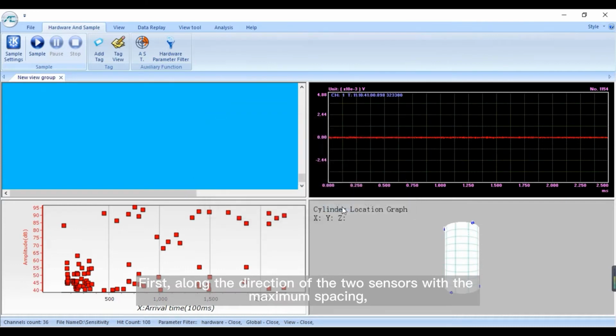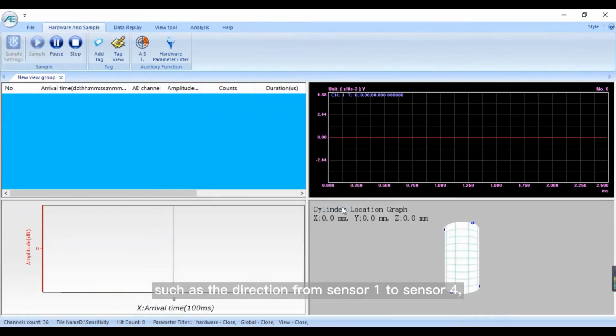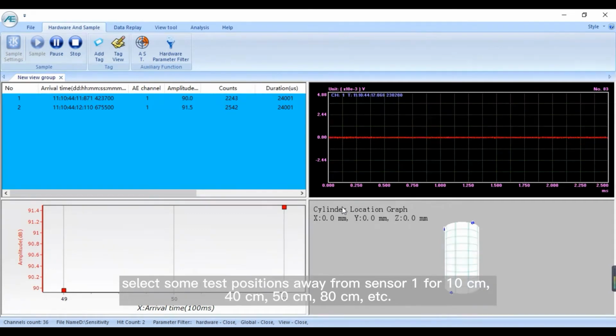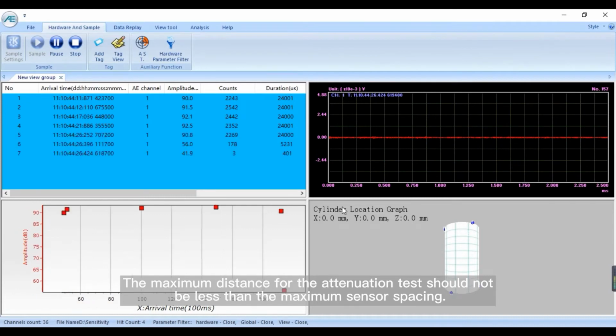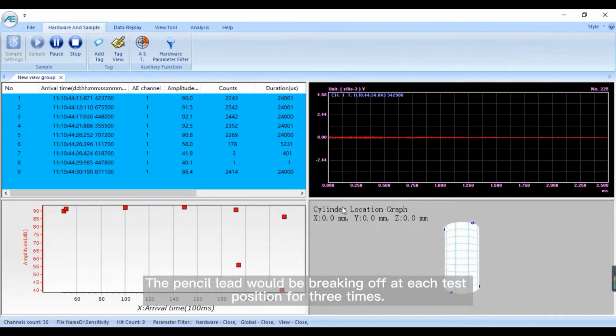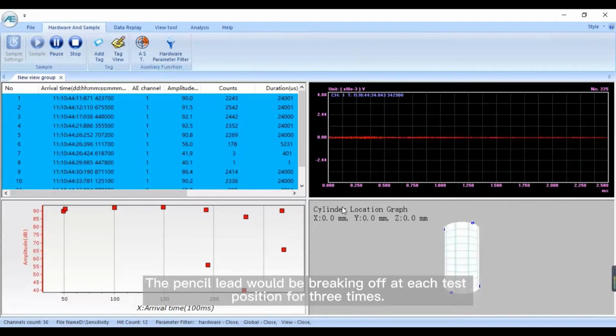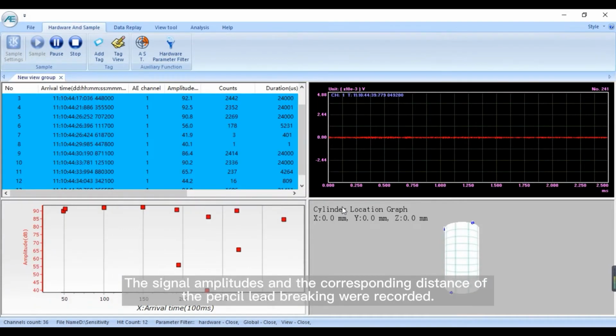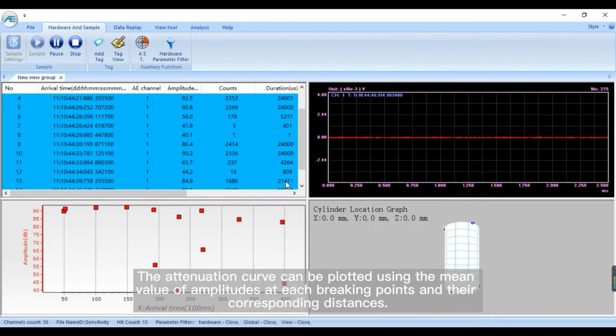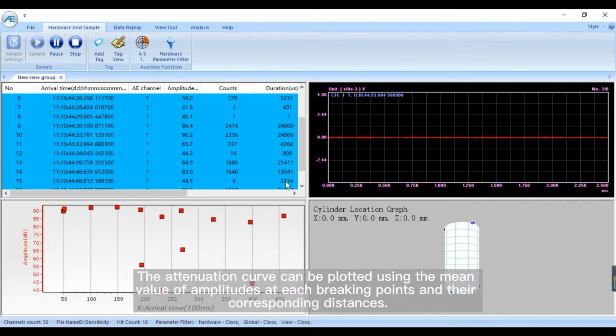First, along the direction of the two sensors with the maximum spacing, such as the direction from sensor 1 to sensor 4, select some test positions away from sensor 1 for 10 cm, 40 cm, 50 cm, 80 cm, etc. The maximum distance for the attenuation test should not be less than the maximum sensor spacing. The pencil lead will be broken at each test position 3 times. The signal amplitudes and the corresponding distance of the pencil lead breaking were recorded. The attenuation curve can be plotted using the mean values of amplitudes at each breaking point and their corresponding distances.